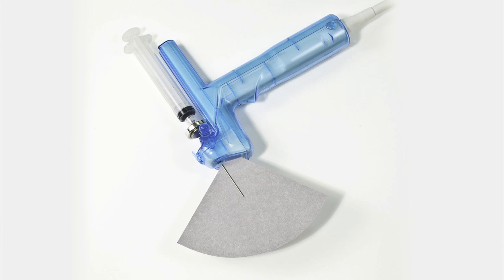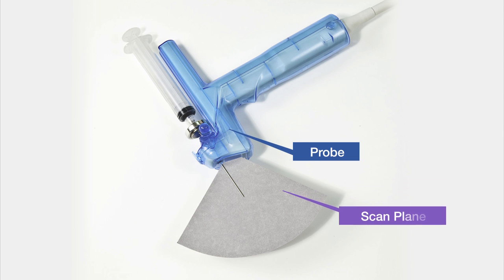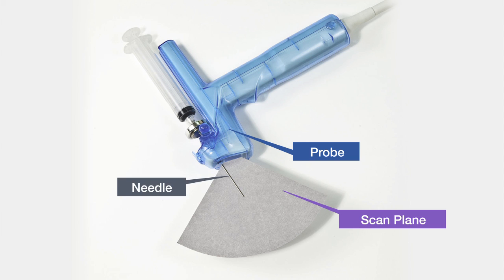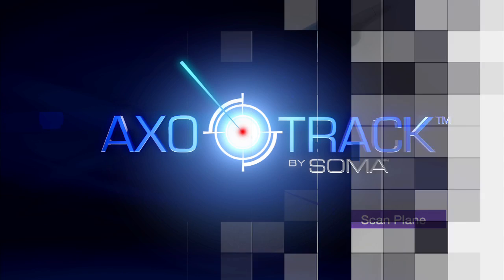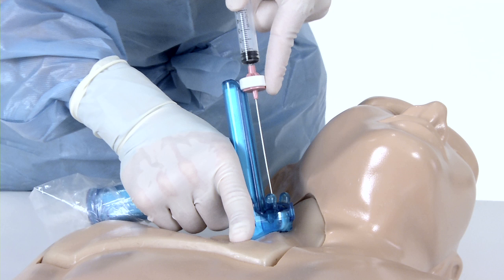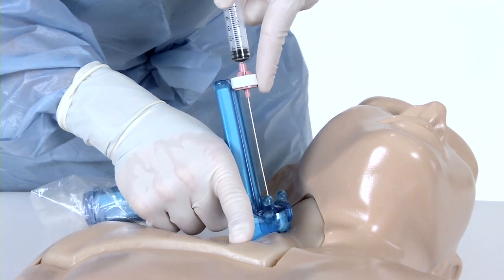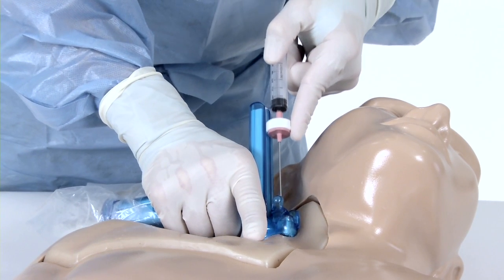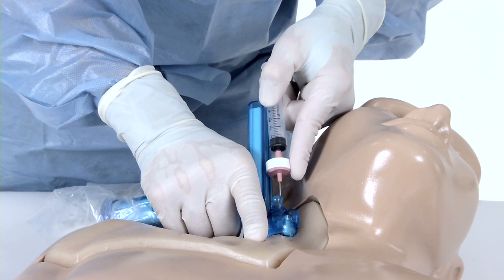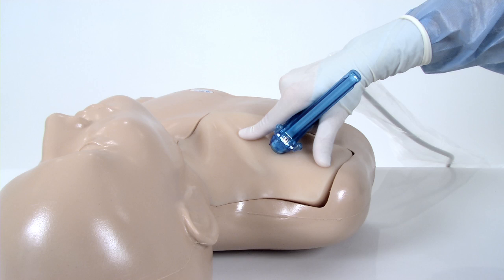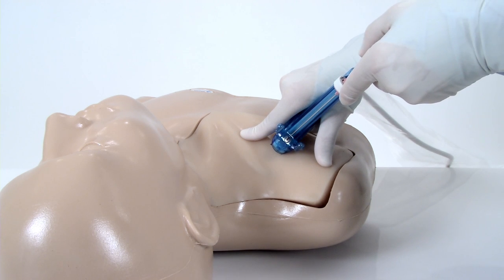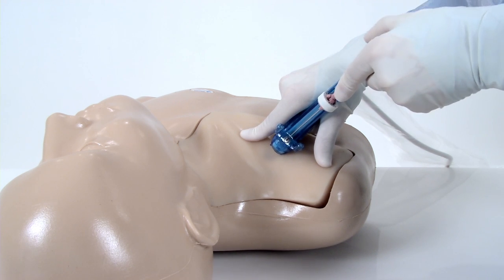When using the AxoTrack-equipped ultrasound probe with virtual needle technology, it is important to understand the relationship between the orientation of the ultrasound probe, the scan plane, and the trajectory of the needle. Note that the trajectory of the needle always lies within the scan plane and corresponds to the direction that the probe is aimed or pointed. The probe does not have to be oriented perpendicular to the body. It can be tipped or angled to find the appropriate window for safe needle penetration, providing tremendous flexibility when approaching needle-guided procedures. Placing the probe on an angle to the body surface is particularly important when performing vascular access.